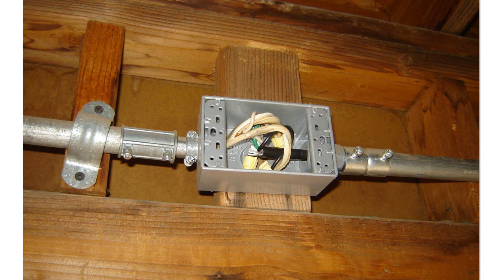This picture here is just wrong in so many different ways. A lot of the stuff you might be able to just figure out, but this box was a half inch box and it's got just slip couplings. I don't know what they were thinking here, but they just used some EMT couplings and slid them over the half inch, and we know that's just not right. Inside here as well, the box wasn't even grounded. We've got UF cable going out to the pool motor, and I think this was off the cord that went to the swimming pool light, and that goes back to the switch.